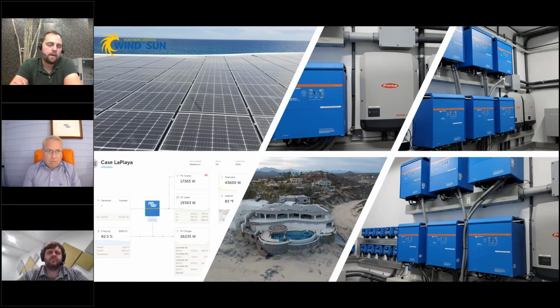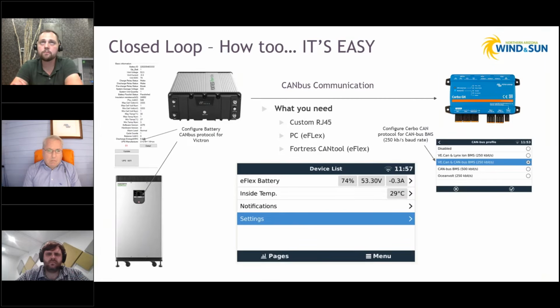I want to quickly touch on how easy it is to set up closed loop communications between Victron and Fortress before handing this off to John. The basic principles of closed loop are as follows: you need to configure the battery to communicate properly. The battery and the GX device communicate using CAN bus communications. Think of it as a language, and the batteries need to speak the correct language that the Victron GX device is interpreting. So it's just setting the communication protocol correctly on the battery side, configuring the device to receive that communication properly, and plugging the two together. It's really as simple as that.